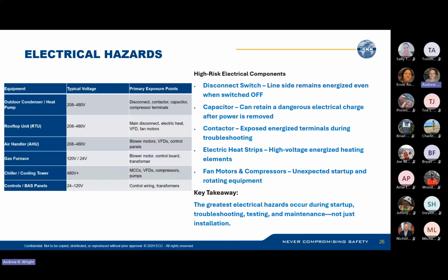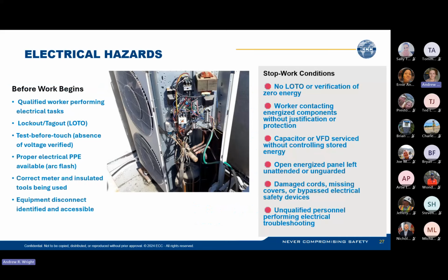All right, so electrical. Before work begins, make sure your qualified workers are performing the electrical tasks. Make sure you're implementing lockout, tagout as needed, and we'll get into that more. Test before touch, which basically means contact testing the switches and terminals, making sure that they are in fact off before you start touching them. Proper electrical PPE like arc flash PPE, your gloves and your suits and your masks as needed. The correct meter and insulated tools being used. The equipment disconnect identified and accessible.